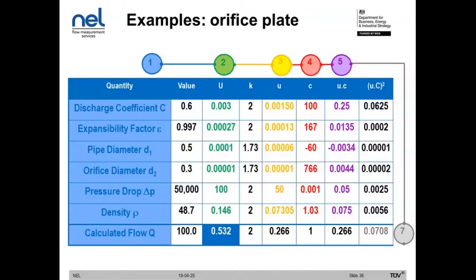we work backwards from right to left. So we can work backwards to find our standard uncertainty of 0.266, and if we want to convert to a 95% confidence level, again, we have to multiply by the coverage factor. So moving from right to left, we move from a standard uncertainty of 0.266 to an expanded uncertainty of 0.532. So this gives a numerical example of how this process is followed, and this is really the process that we use for our own flow facilities to develop that evidence.